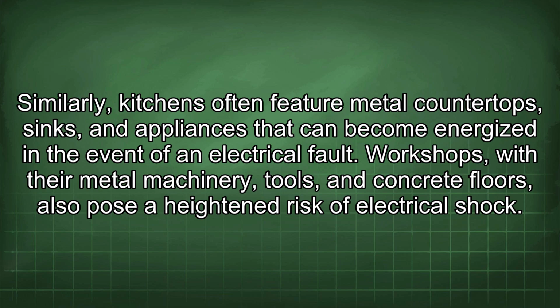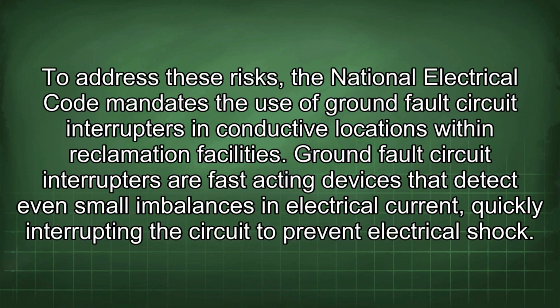Similarly, kitchens often feature metal countertops, sinks, and appliances that can become energized in the event of an electrical fault. Workshops, with their metal machinery, tools, and concrete floors, also pose a heightened risk of electrical shock. To address these risks, the National Electrical Code mandates the use of ground fault circuit interrupters in conductive locations within reclamation facilities. Ground fault circuit interrupters are fast-acting devices that detect even small imbalances in electrical current, quickly interrupting the circuit to prevent electrical shock.